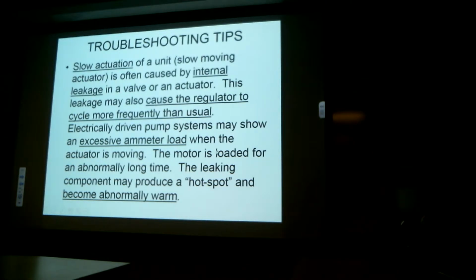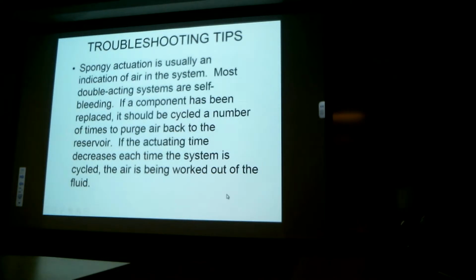The motor is loaded for an abnormally long time. The leaking component may produce hot spots and become abnormally warm. This is true a lot of times with pumps where you've got an excessive amount of clearance. The stagnant fluid that's not able to be exchanged into the circuit or back to the reservoir causes the pump to overheat. So a lot of pumps that are excessively worn will become a little bit warmer than normal.